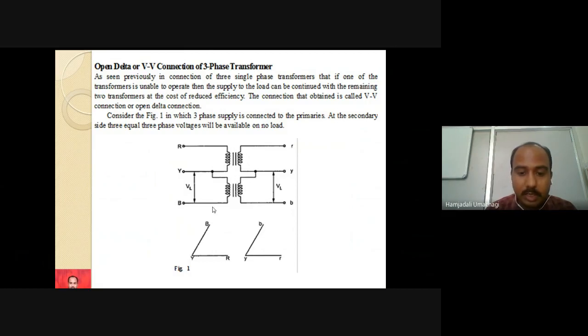Why is it VV? Because it looks like the English letter V. Because of that reason we call this connection VV connection. But when one of the transformers goes out of service, it should be operated with a reduced loading condition. You should not apply the same load, because now there are only two transformers that can serve the purpose. For that sake, how much load it can carry effectively, we can see here in this open delta VV connection explanation. Okay.